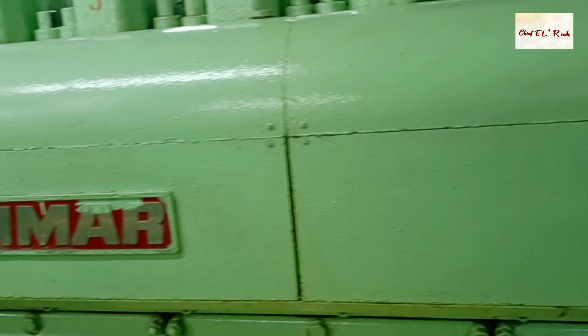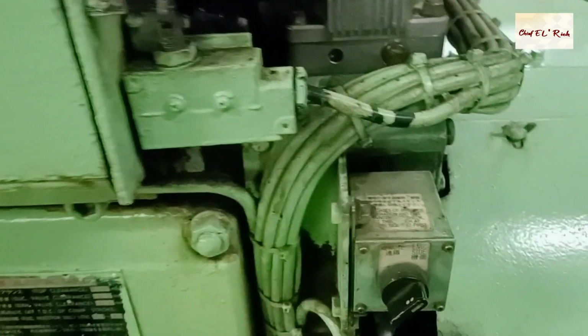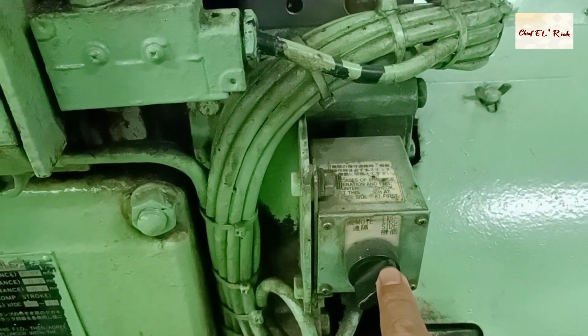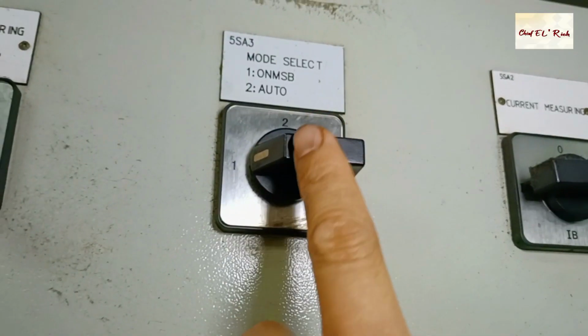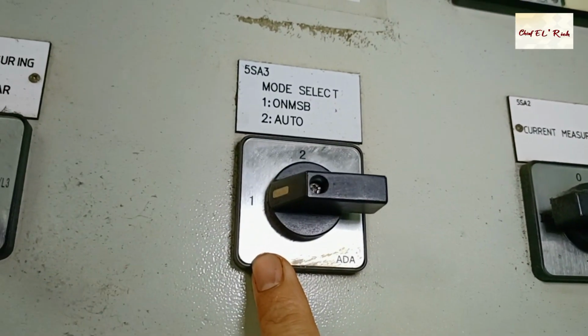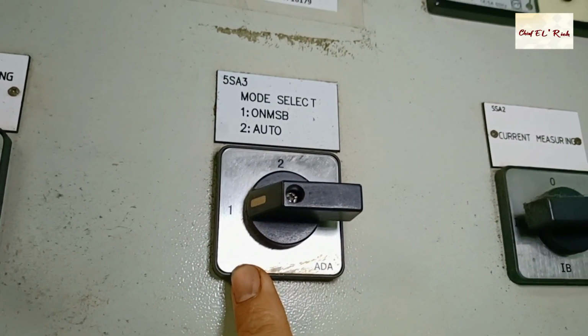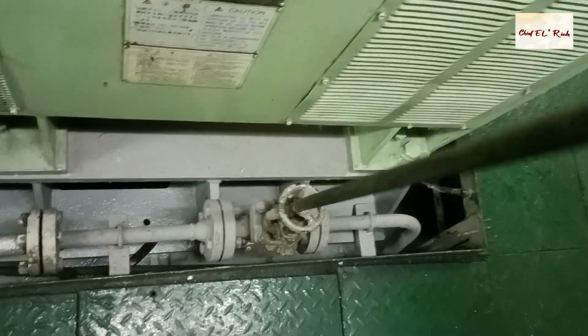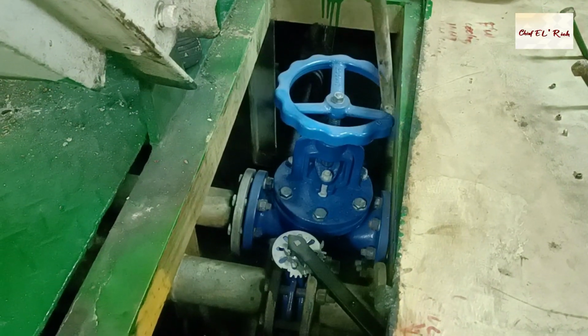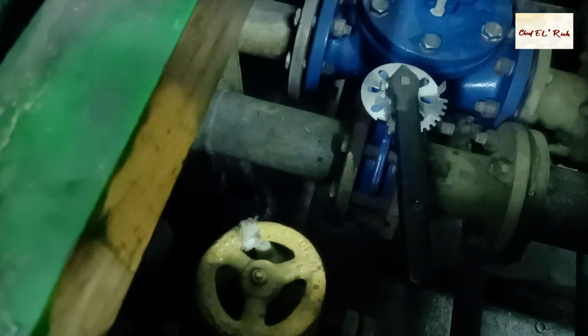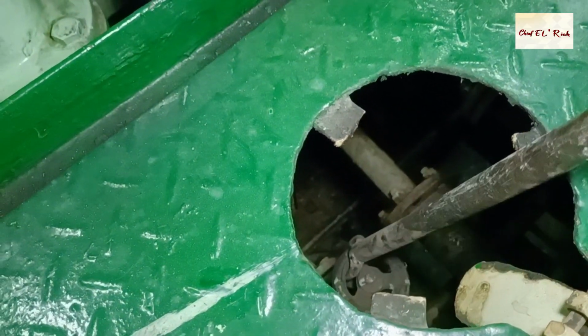First thing to do is we will secure the engine in order not to run in automatic mode. Change the selector switch from automatic to engine side. Then change the selector switch in the engine control room main switchboard from automatic to main switchboard manual.